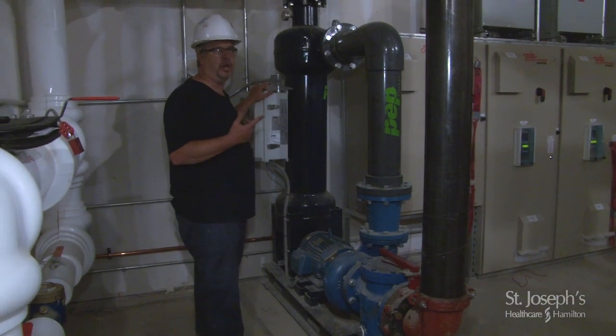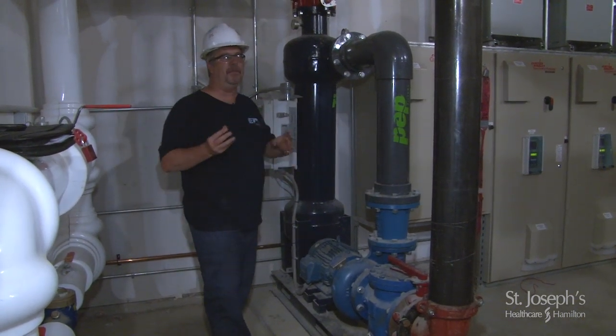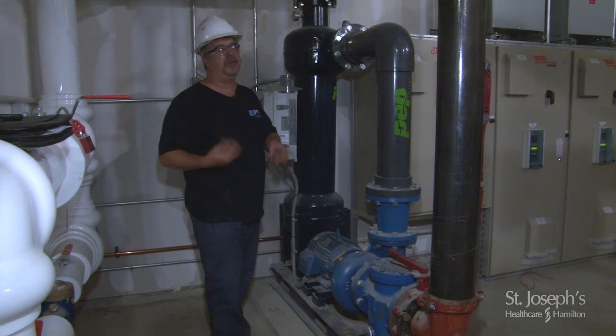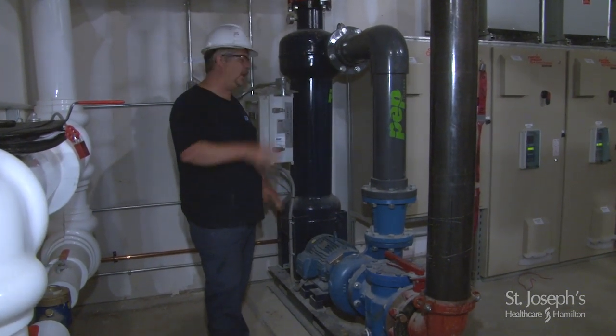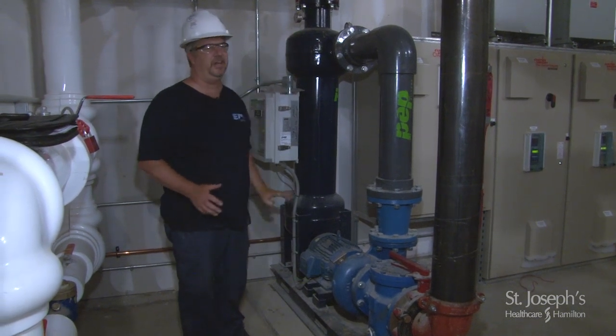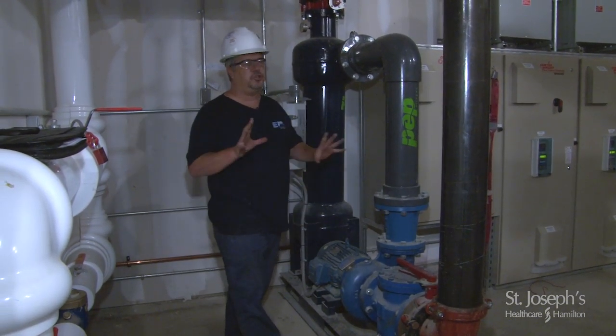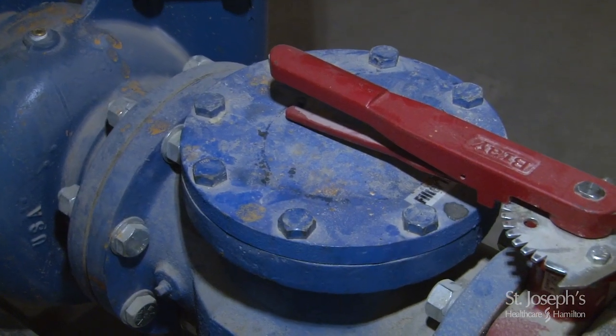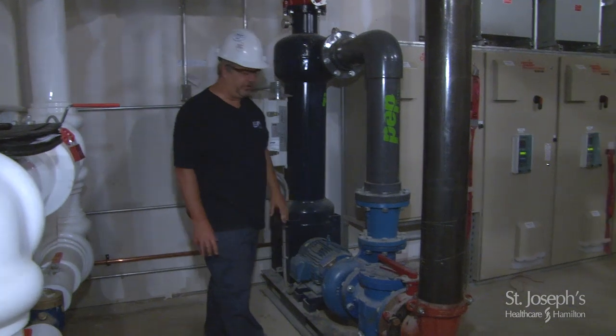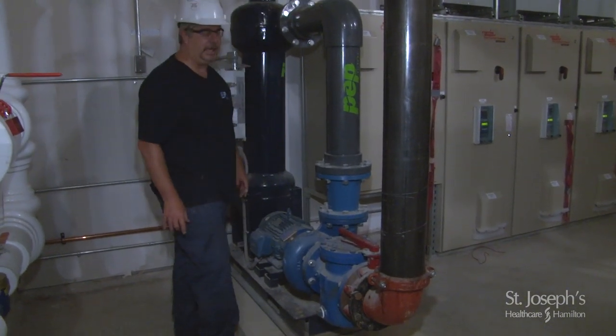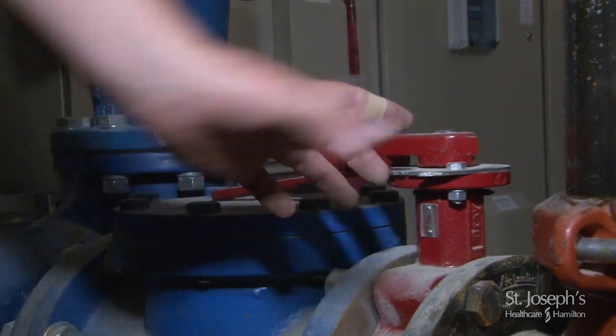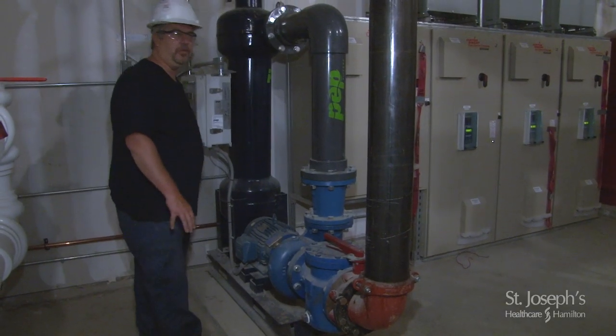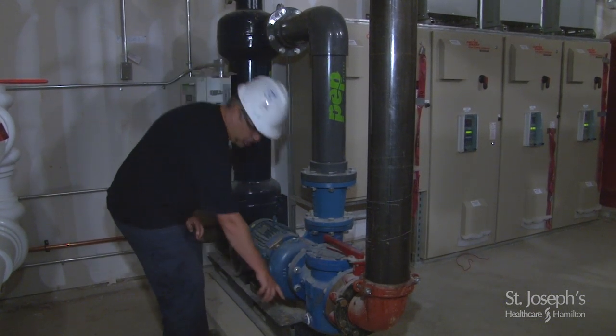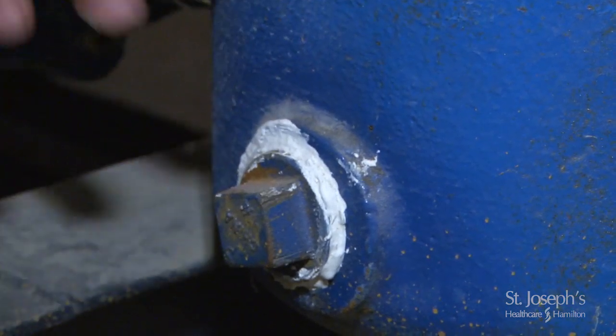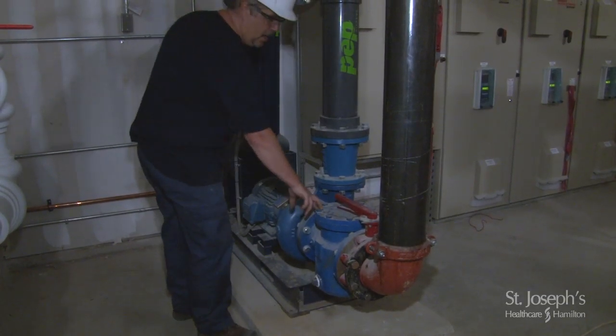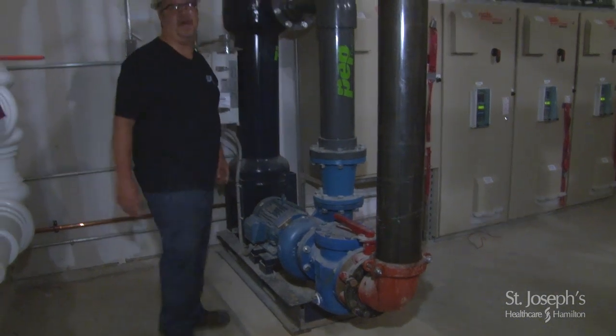If you find the unit purging on a continuous level, what I mean by that is it purges, it comes out of purge, and then almost immediately goes back into purge. That's because it's seeing a blockage or it's not liking the pressures that it's seeing. Good chance your problem is within this filter at the beginning of the filter assembly. To check this filter and to clean it, what we want to do is take the red valve, shut that off, turn the tower off, shut the pump off, put that into the off position. You can open up this valve at the bottom, which will relieve a little bit of the pressure that might be built up in there, and then using a wrench, take the top off of that assembly.